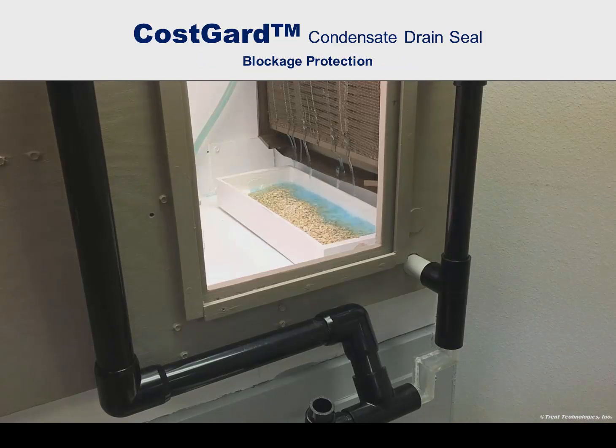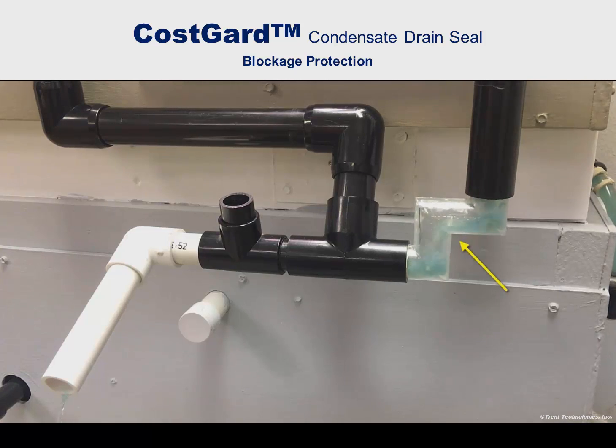Perhaps the most recognized problem with a condensate trap is that it catches debris and becomes blocked. This happens frequently, often after only a few months of operation. The CostGard condensate drain seal inherently guards against such blockage. This special CostGard device, equipped with clear plastic elbows, shows why. Here, soggy oatmeal is used to simulate the slime that often clogs drain lines and traps.